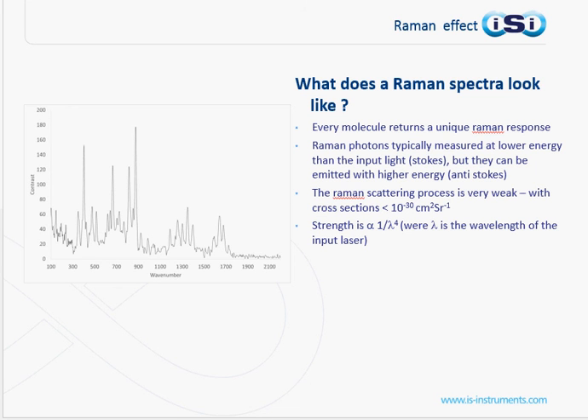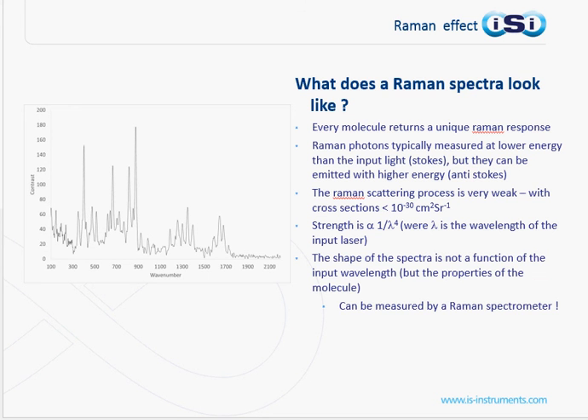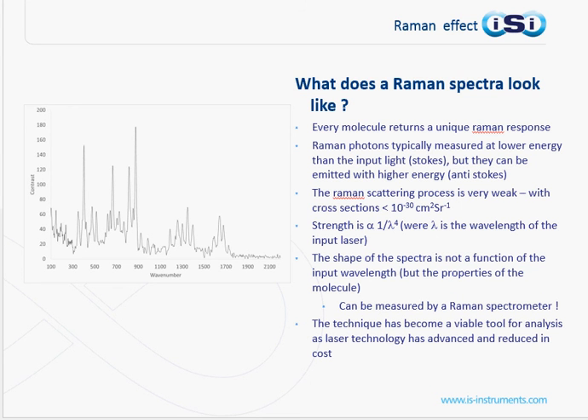However, other effects occur when you measure at shorter wavelengths — for example at 532 nm — such as fluorescence, which can contaminate the signal. The shape of the spectra is not a function of the input wavelength, but of the properties of the molecule itself, and it is this that can be measured by a Raman spectrometer. The technique has become a viable tool for analysis in recent years as laser technology has matured and dramatically reduced in cost.